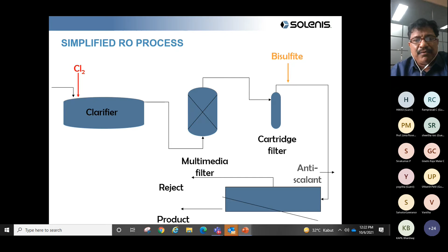Now, a thumb rule for a layman is that one membrane can handle 0.8 cubic meter per hour. So if I need to treat, say, 80 cubic meter per hour, I would need about 100 membranes. Each membrane will treat about 0.8 cubic meter per hour. But obviously you can't have membranes hanging in the air. So we decide to put about 4 or 5 membranes in a pressure tube, so that you compact the operations.